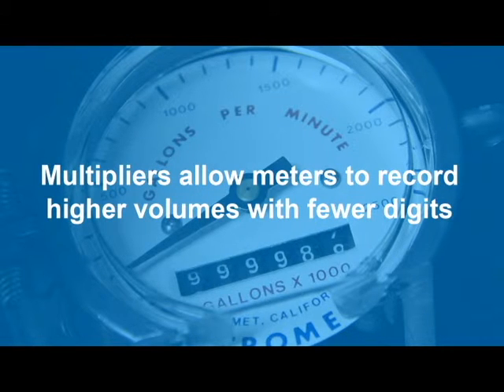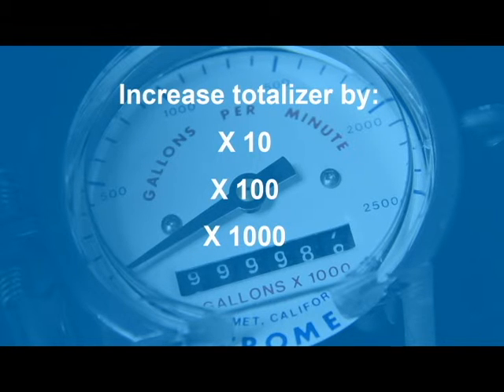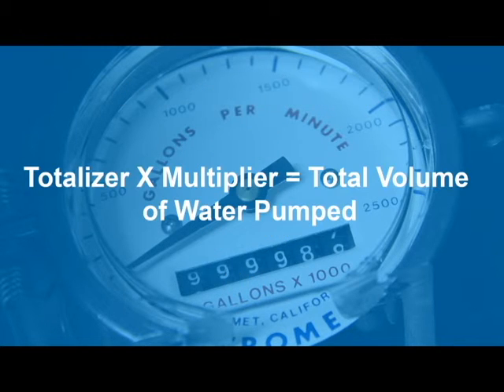Multipliers allow the meters to record higher volumes with fewer digits and may increase the totalizer reading by ten, one hundred, or a thousand times as in the case of this McCrometer propeller. Some meters may even have a multiplier of one. After multiplying the reading on the totalizer by the multiplier, you have successfully read the meter. Congratulations! We have now concluded this tutorial on McCrometer propeller mechanical flow meters. For more information, please contact us at pr.northplainsgcd.org. Thank you.